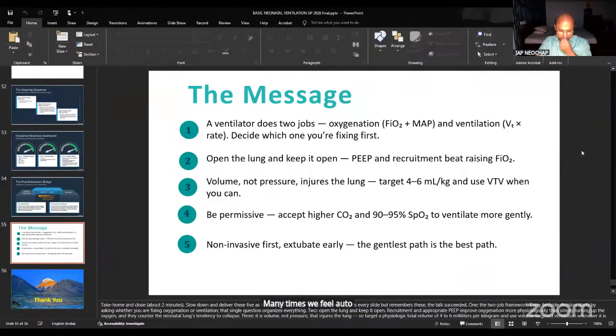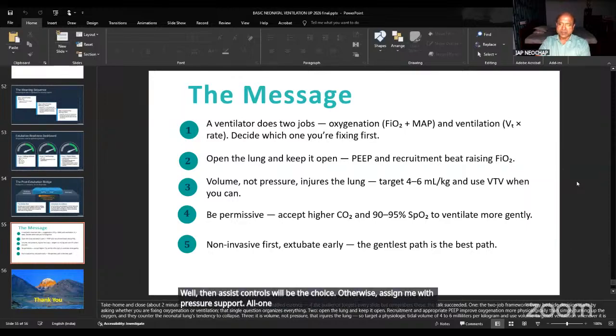If for any reason you have set the trigger very low, or there is condensate in the tube, it will cause it. If you take care of auto triggering, then assist control should be the choice. Otherwise, SIMV with pressure support. Alone SIMV, nowadays people don't use it. I will also not advocate for that.